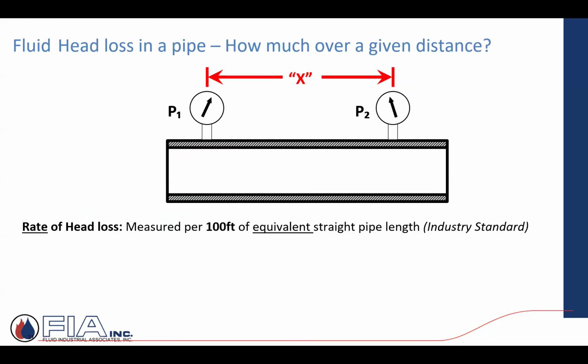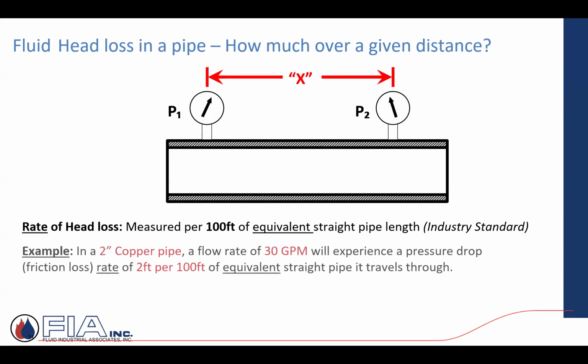Fluid head loss in a pipe. How much over a given distance? Rate of head loss. It's kind of an industry standard, but they'll say it's measured in 100 feet. So what's your pressure drop in feet per 100 feet of pipe? When we look at sizing later on, next week, if you look at pipe sizing charts, they typically will always reference feet per 100 feet of pipe, or TEL, total equivalent length.